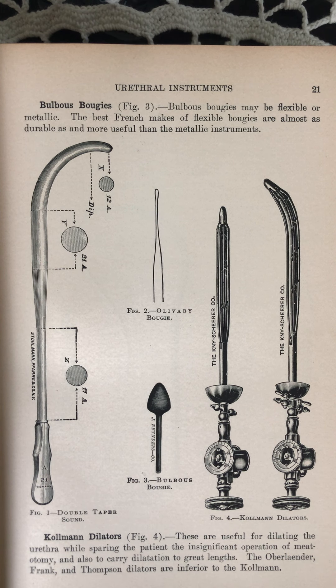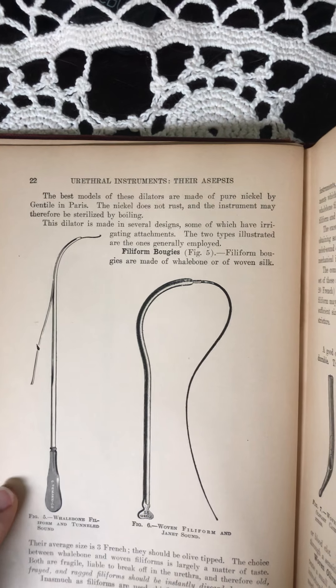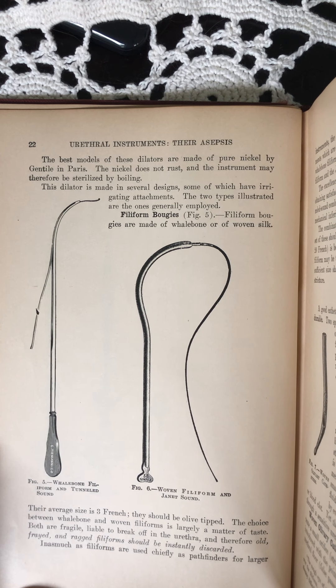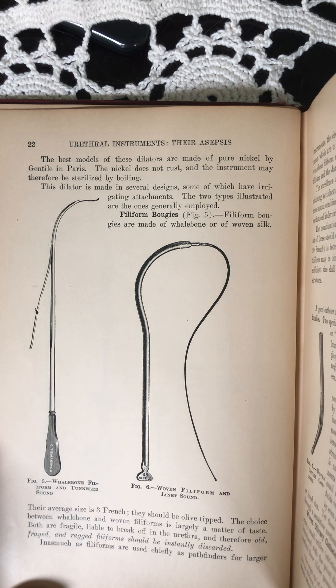Kollmann dilators are useful for dilating the urethra while sparing the patient the insignificant operation of meatotomy, and also to carry dilatation to great lengths. The Oberlander, Frank, and Thompson dilators are inferior to the Kollmann. The best models are made of pure nickel by Gentile in Paris. The nickel does not rust and the instrument may therefore be sterilized by boiling. This dilator is made in several designs, some of which have irrigating attachments. The two types illustrated are the ones generally employed.